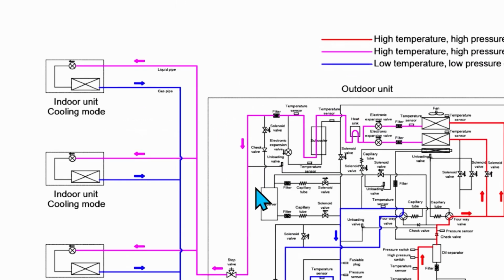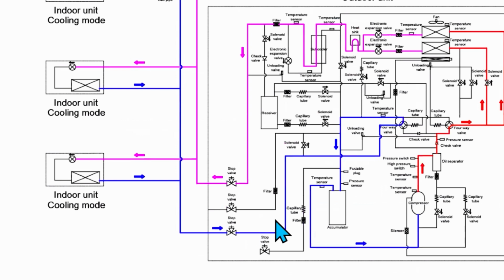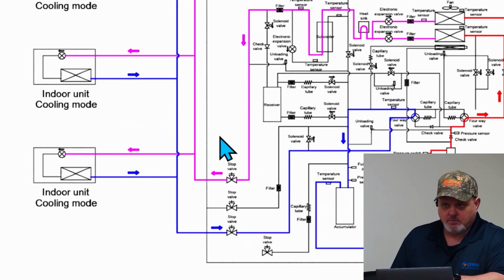So when you follow the piping through, and that's where I say it's a little bit confusing, we're using liquid and high pressure gas. So the sequence there is not exactly the same. That's why it's so important. That's why we pointed out in the beginning in the owner's manual, that's the only place that it clearly tells you in a heat pump which 2 service valves you hook up to for heat pump only.